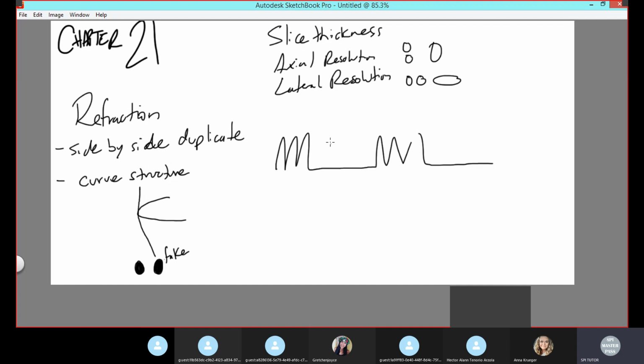And this is determined by depth, right? If I am deep in the body, then I have a big off time because I have to wait for everything to come back. There may be something that comes back from this pulse that should have been here, but it came back a little too late, and now it comes back here. That reflection should have come back right before you send out the other pulse, which would mean it is very deep in the body because it came almost at the last second. It took a very long time to come back. That's why it's deep in the body. But instead, it came back after the next pulse was sent out, immediately after.